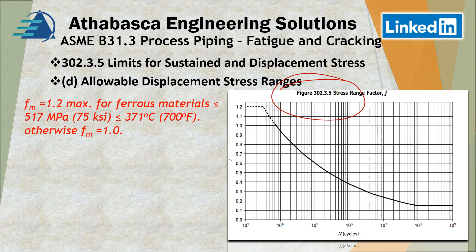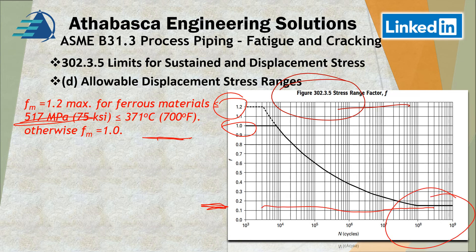Section 302.3.5 graphically represents the stress range factor. For FM of 1.2, shown for ferrous materials under those conditions, otherwise use 1.0. You can see that for a very low stress range, the minimum of 0.15 corresponds to the part of the curve for an infinite number of cycles. This is just like the fatigue curve discussed in the introduction slides, and this is how the code guides avoidance of fatigue-related issues.